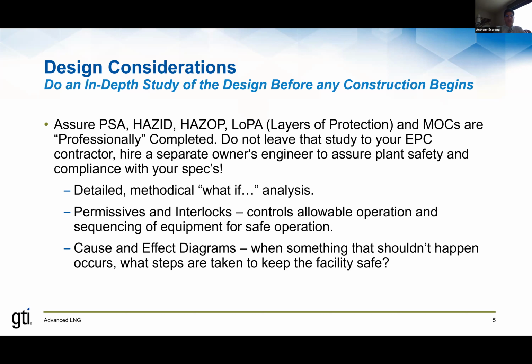One of the ways you do that is with systems that are interlocks and permissives, meaning that you have areas in your plant where a particular valve might not open unless a particular temperature condition is met, or a particular pressure condition is met. So even if the operator tries to open a valve in a certain system, that valve will basically check itself and say, hey, wait a minute, should I really open? Are the conditions proper for me to open? And if those conditions aren't met, that valve will not open. That's just an example. When I use a valve, it could be any component within the LNG facility.